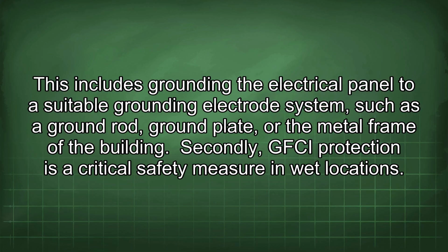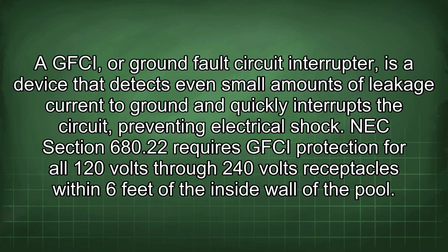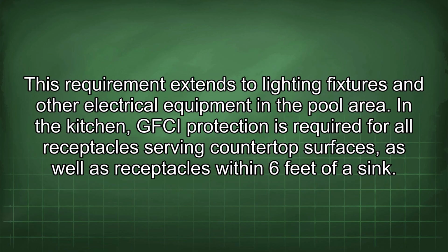Secondly, GFCI protection is a critical safety measure in wet locations. A GFCI, or ground fault circuit interrupter, is a device that detects even small amounts of leakage current to ground and quickly interrupts the circuit, preventing electrical shock. NEC Section 680.22 requires GFCI protection for all 120 volts through 240 volts receptacles within 6 feet of the inside wall of the pool. This requirement extends to lighting fixtures and other electrical equipment in the pool area.